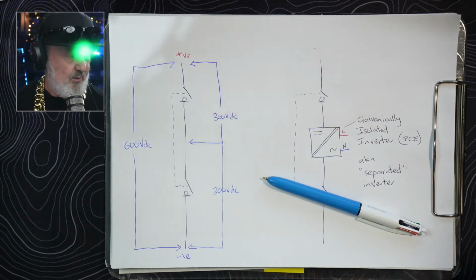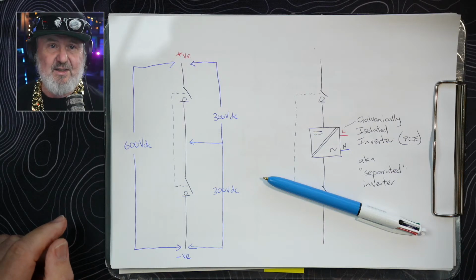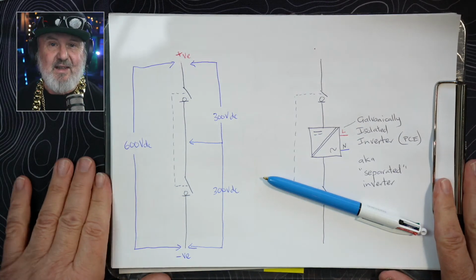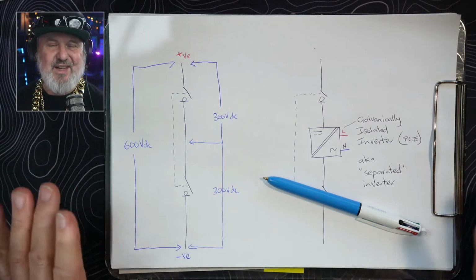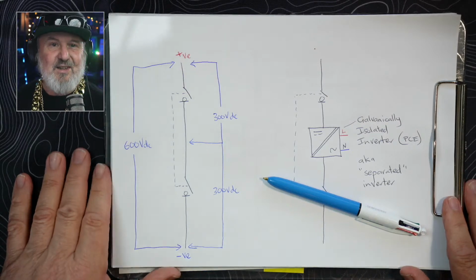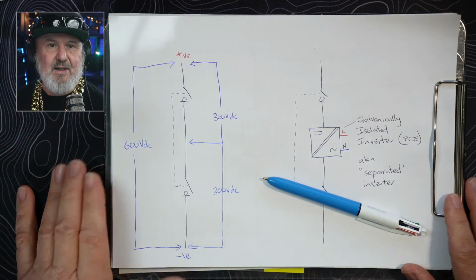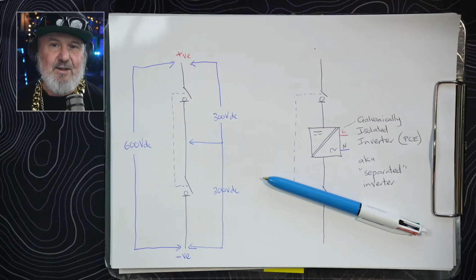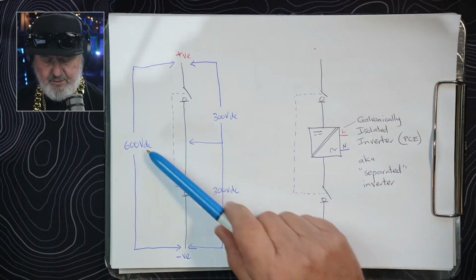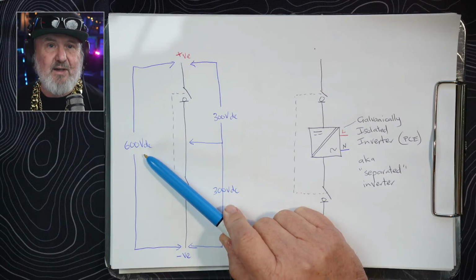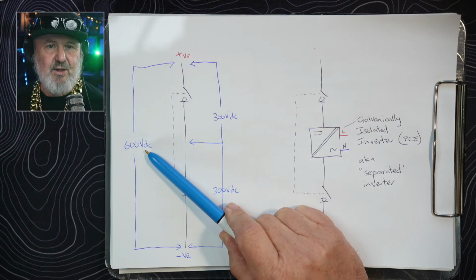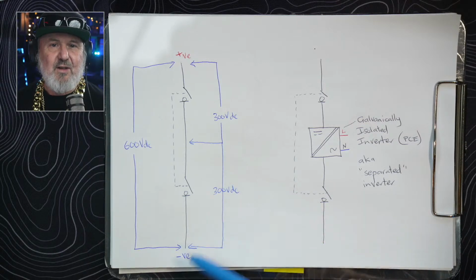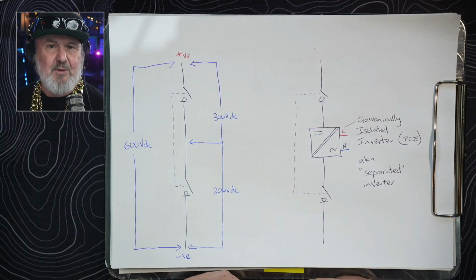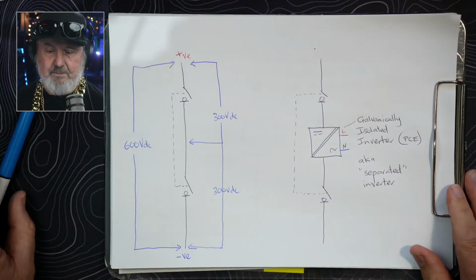The problem with DC isolators, or any device that's used for isolation, is that, for a start, we don't have a standard PV array voltage. We have whatever it is. You actually manufacture the voltage by configuring the number of modules in an array, and you'll come up with a particular open circuit voltage. Now remember, this voltage here is the open circuit voltage of the PV array, and that also has to be temperature compensated. So the colder it is, below 25 degrees Celsius, the higher this voltage goes. So I'm just picking 600 as a nice round number, but it depends on what your array is.